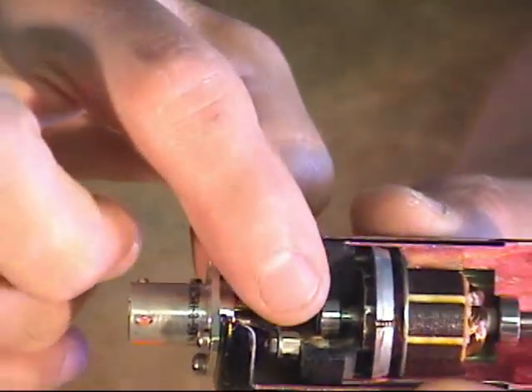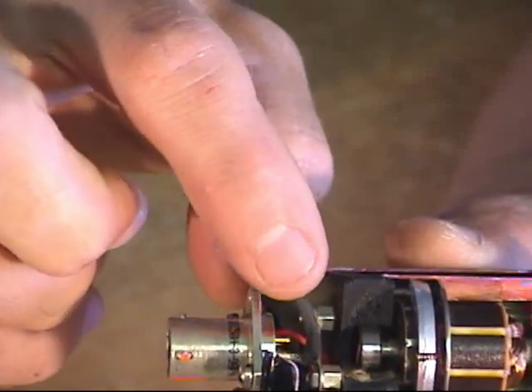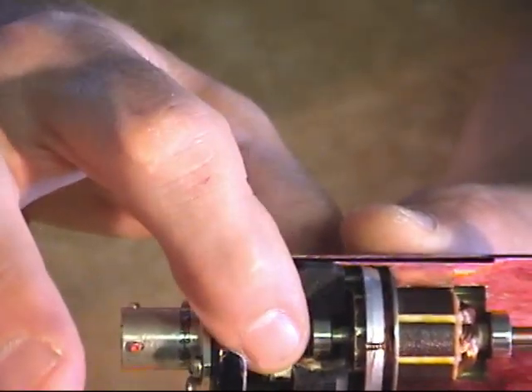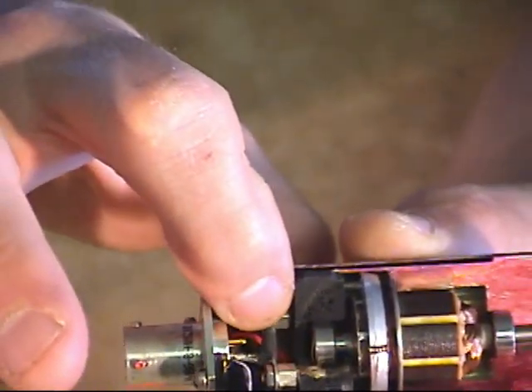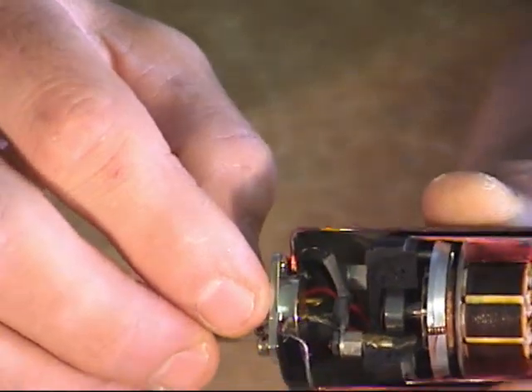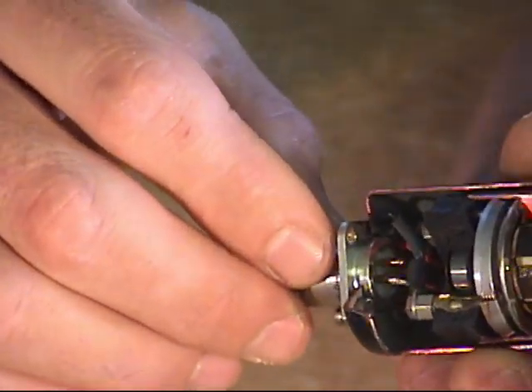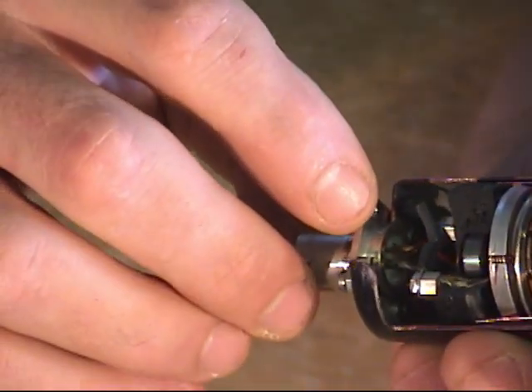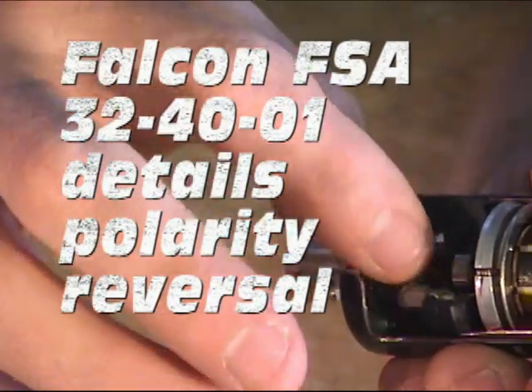These units can be wired backwards and have been wired backwards from the factory. There's 2 little posts here that go to the brushes, and then pin A and pin C over on the plug. They have been wired backwards in the past, which has led to difficulties on the airplane. So some of the tests we do will be testing for polarity of this unit.